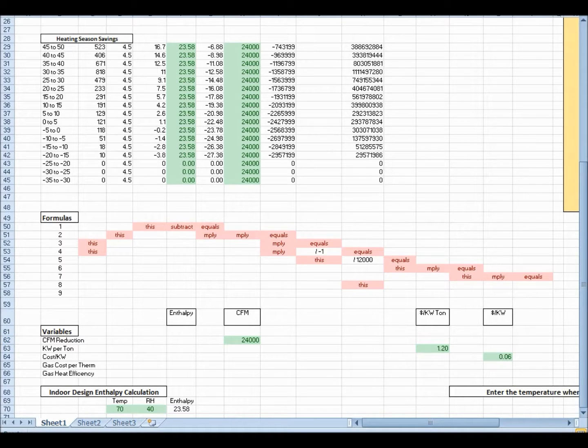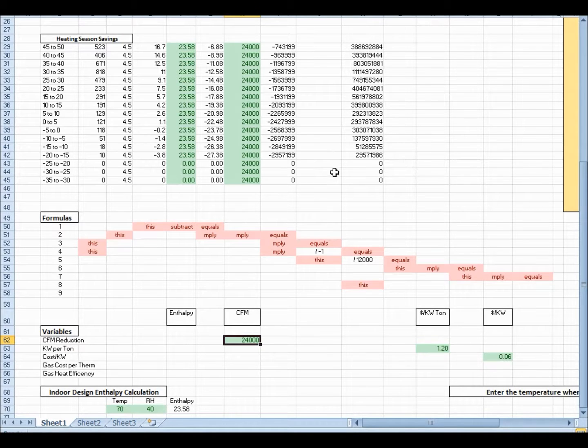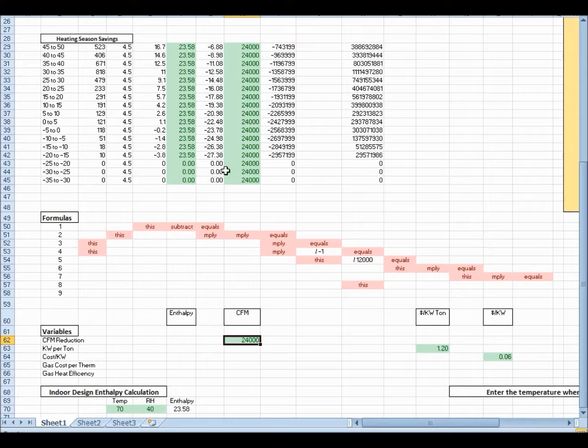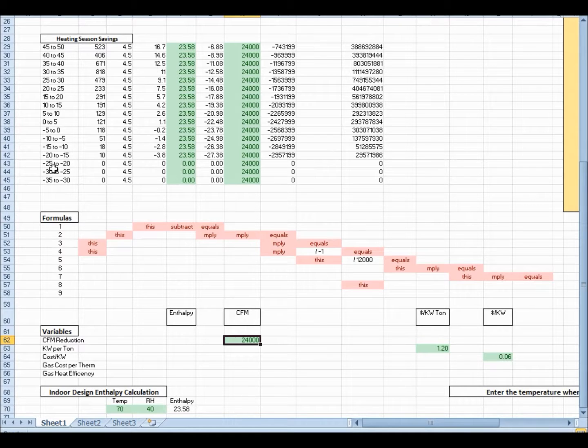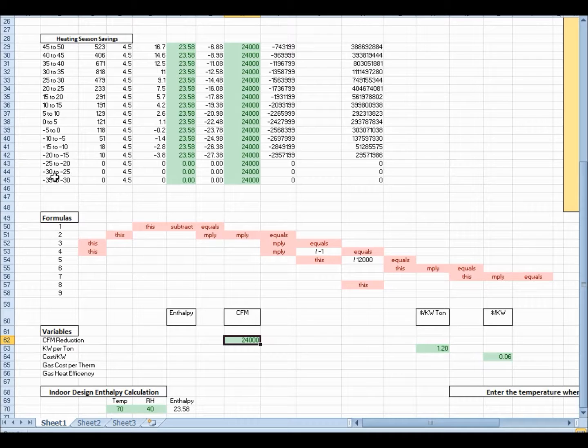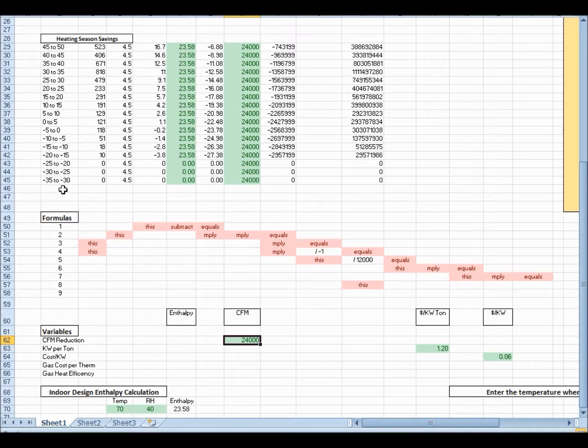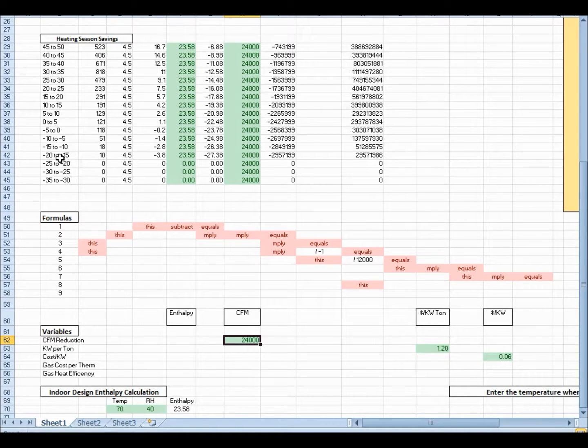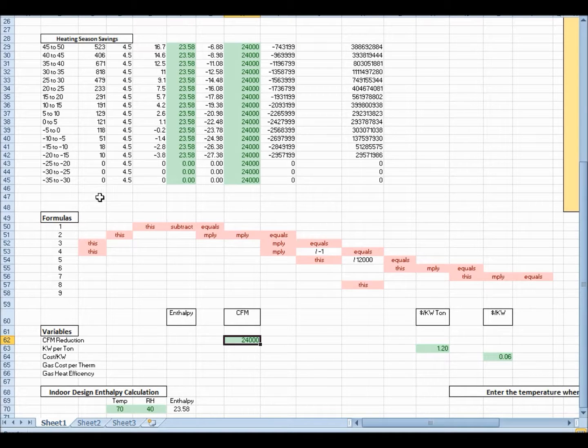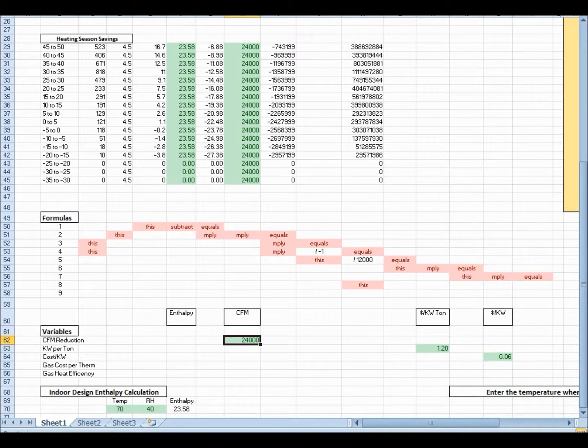You'll also notice that there's some blank spots here. Right here's some zeros, right here's some zeros. If we follow this back, this is the bin data for minus 25, minus 20 to minus 25, minus 30 to minus 25. Right there, Iowa, and we're basing this on Des Moines, Iowa, they don't have any bin data because they never get that low. So, it's zeroed out.